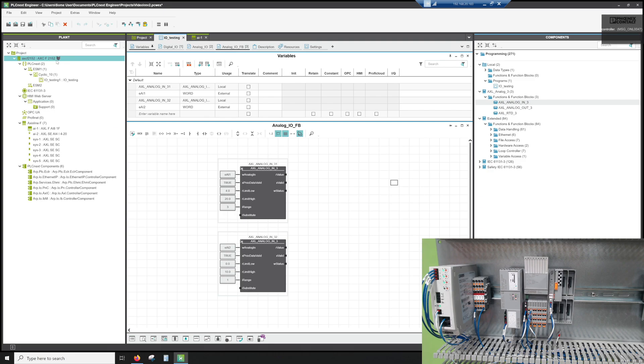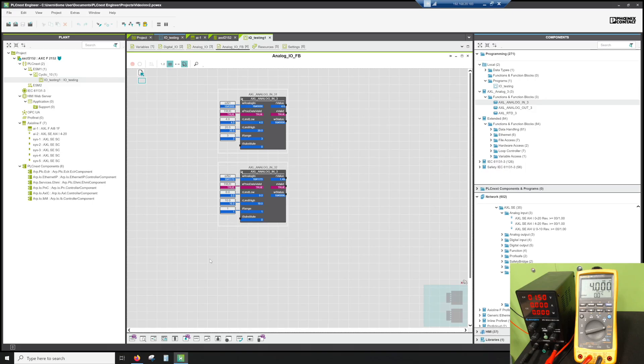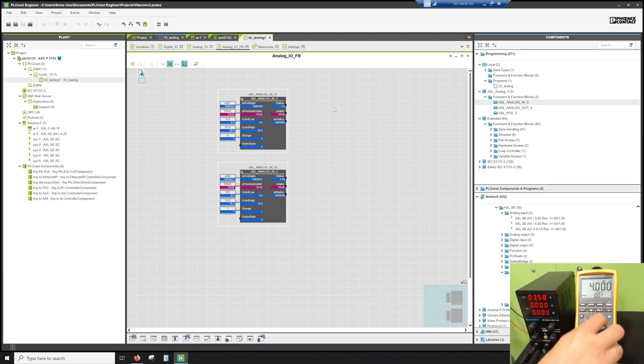Now connected and online, you can see the two analog blocks. The top one is our 4 to 20 milliamp signal and the bottom is our zero to 10 volt signal. At the bottom of the screen you can see we're simulating 4 milliamps and 1.5 volts. Adjusting the voltage shows a change in the block output. Running some stepping drills with a meter confirms we get the same value in the software as on the meter. That's a quick tutorial on analog scaling with an AI8 card.